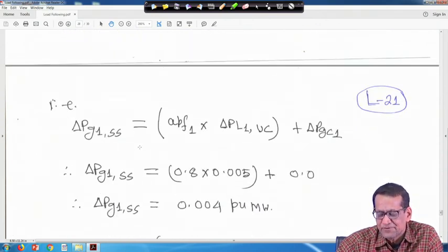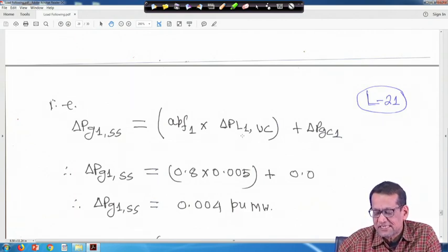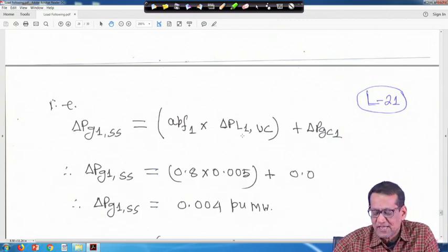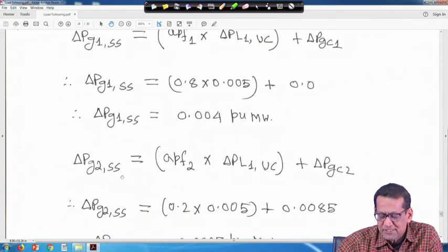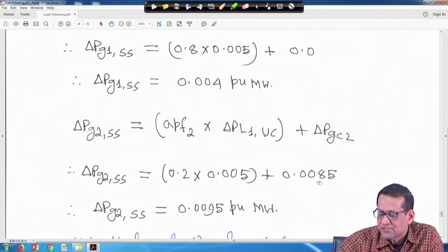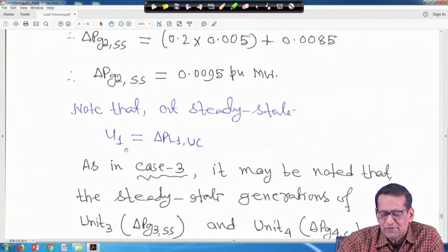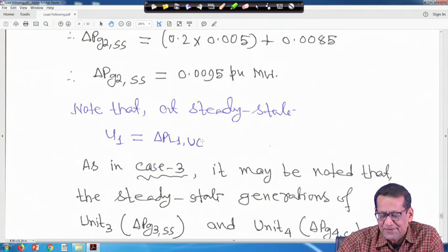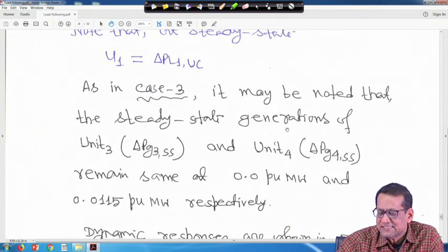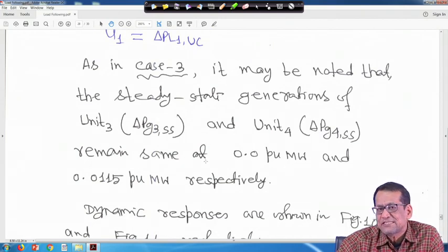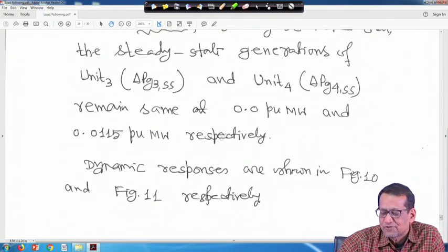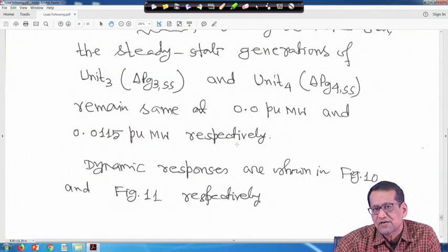At steady state, using equation 18: delta PG1 SS = APF1 × delta PL1 UC = 0.8 × 0.005 = 0.004 per unit megawatt. Delta PG2 SS = delta PGC2 + APF2 × delta PL1 UC = 0.0085 + 0.2 × 0.005 = 0.0095 per unit megawatt. Note that at steady state u1 equals the uncontracted power — you can verify through simulation. As in case 3, the steady state generation of unit 3 and unit 4 remain the same: delta PG3 SS = 0.0 per unit megawatt and delta PG4 SS = 0.0115 per unit megawatt.